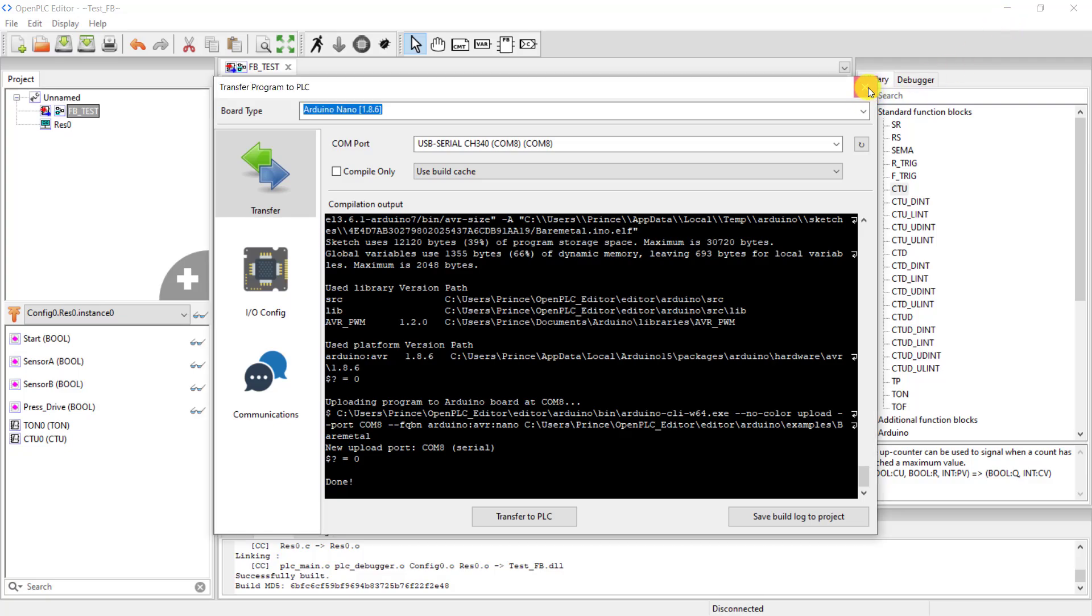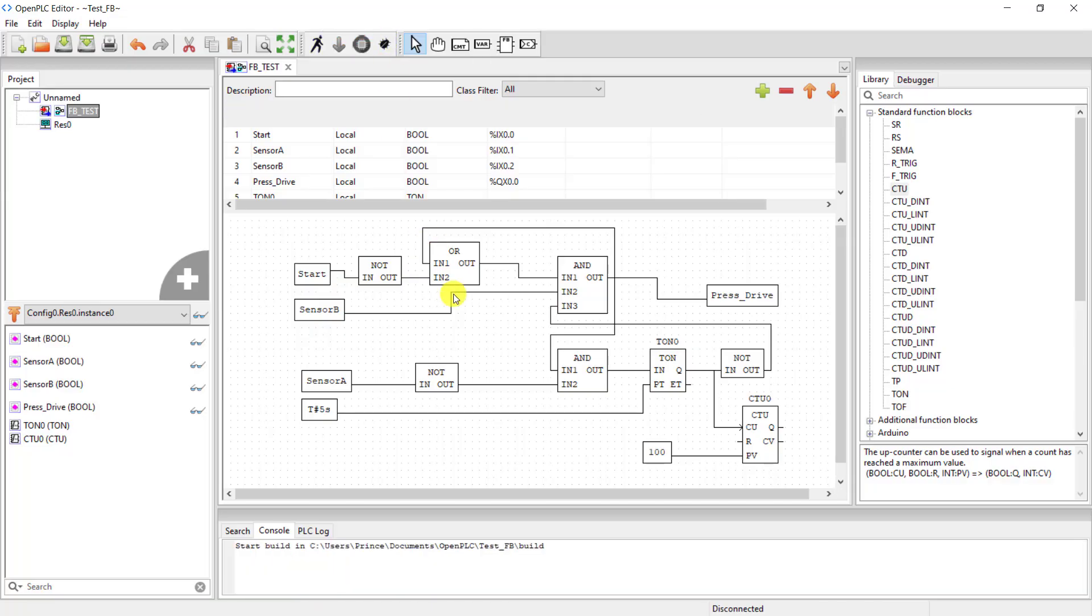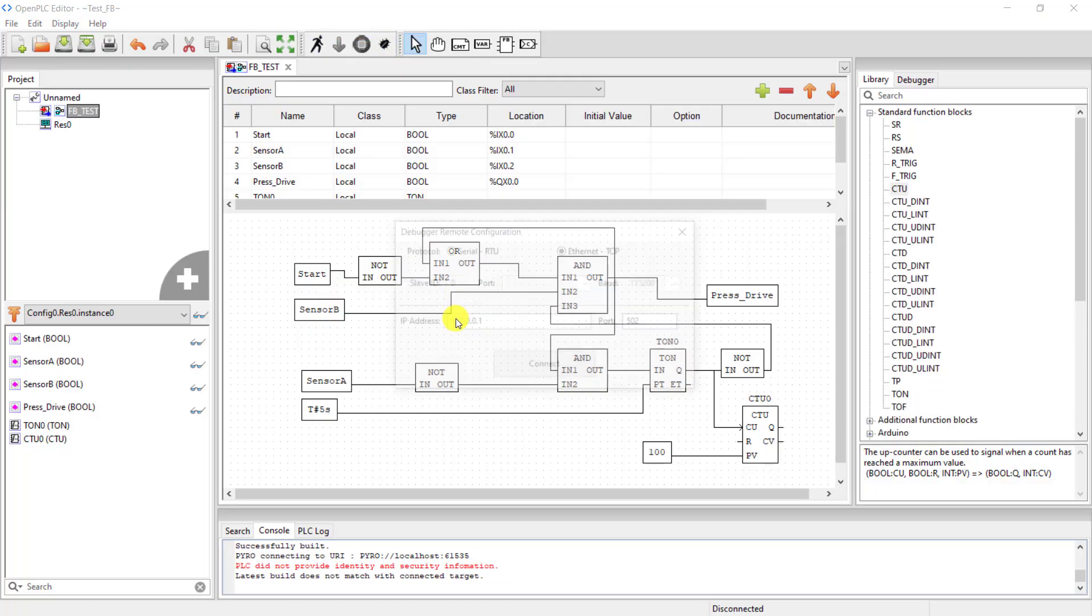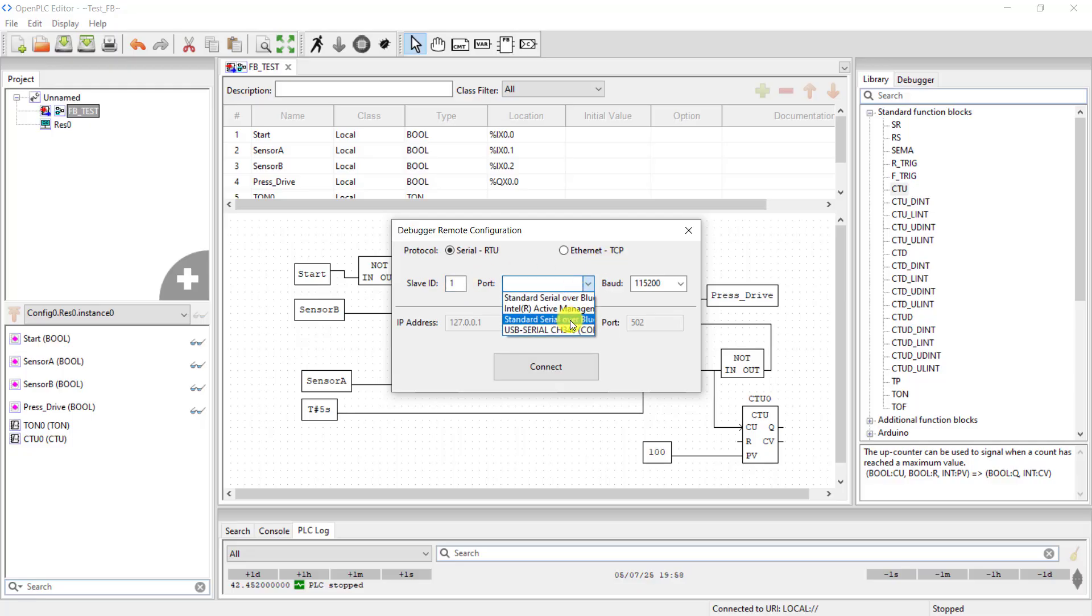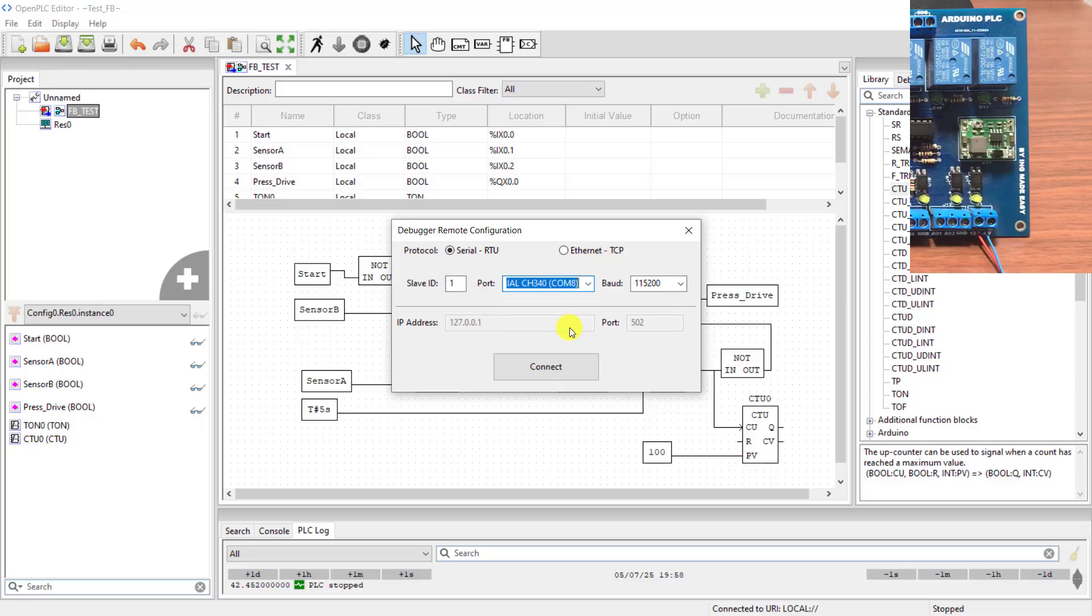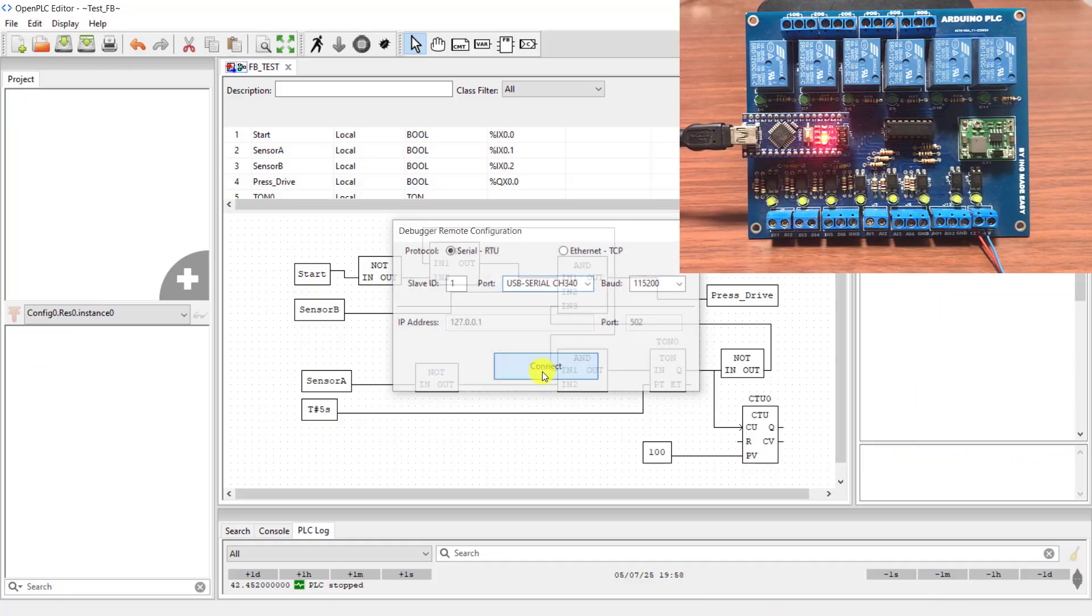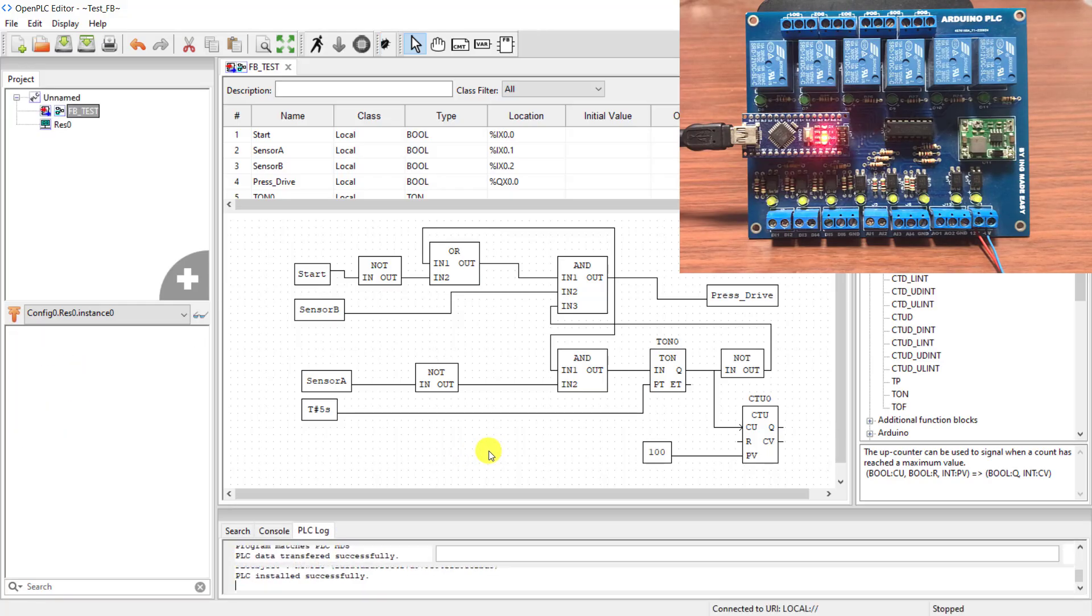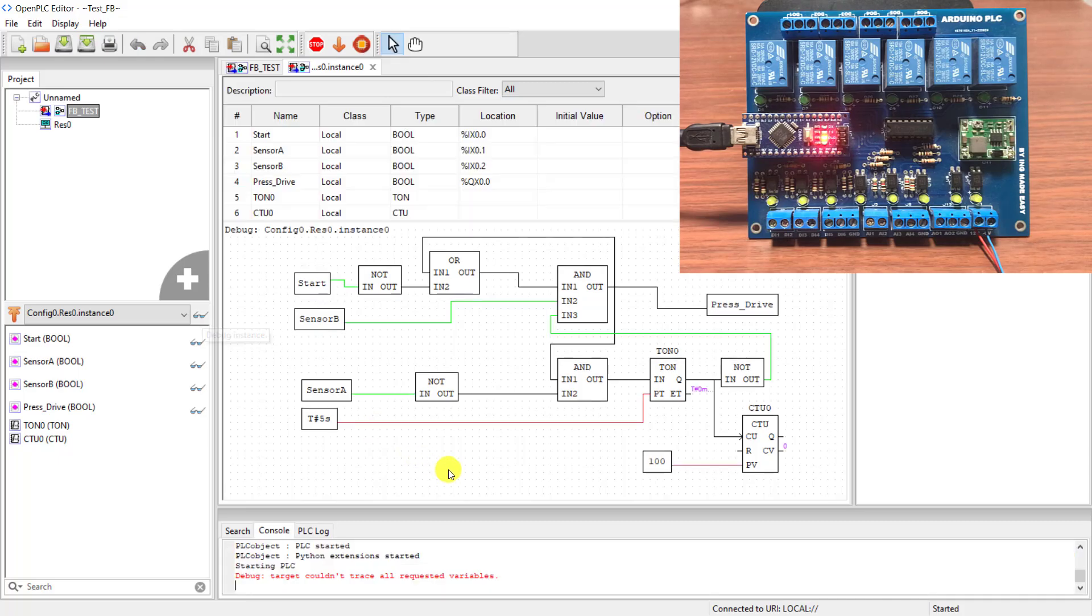Now I close this particular window and now let's monitor using the debugging. I click on the debug. Okay, I have this interface. I select the serial RTU, change the ID to one, and then select the port. The baud rate remains the same. I click on connect and we can see activity on the board indicating that it is connected. And now put on the goggles to go online and we can see what is happening within our PLC.